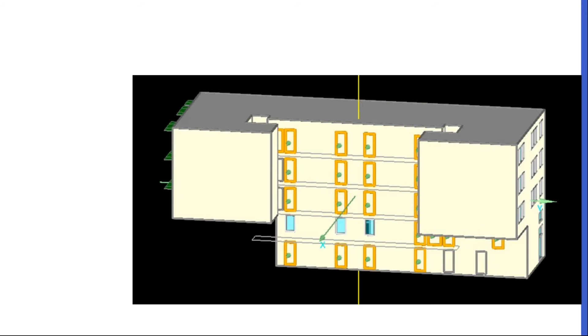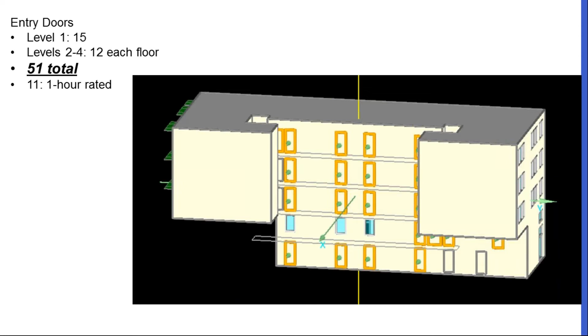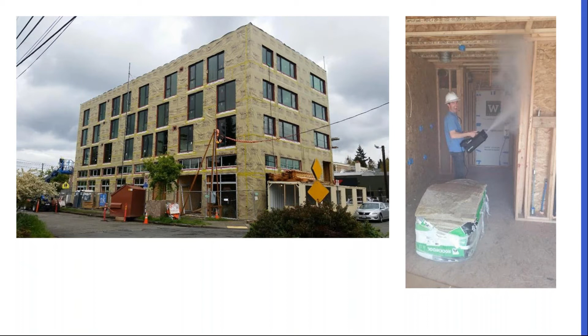When do you do your blower door systems, when do you get access? They're roughing in the plumbing and putting in drywall on one floor, but roughing in the plumbing on the other. So we did about 10 blower door tests on this building, but the only time we ever got to use the manometer was limited, so otherwise it was just using smoke. We were in there all the time, chasing and chasing, but it was the only way we could get into the building and really make sure. We luckily got there at the very end.